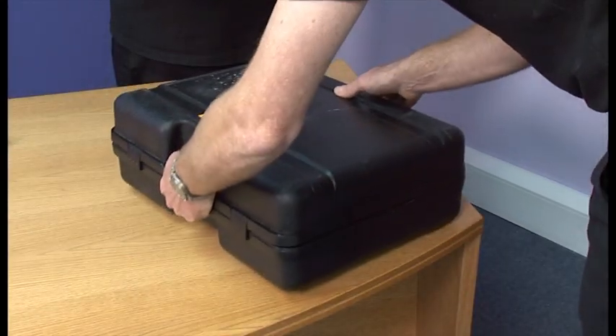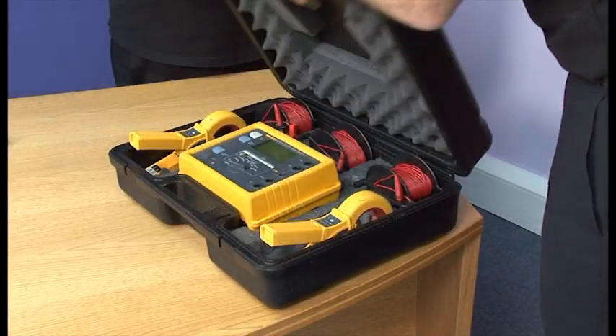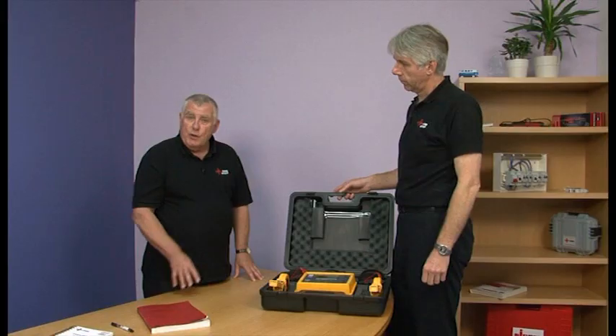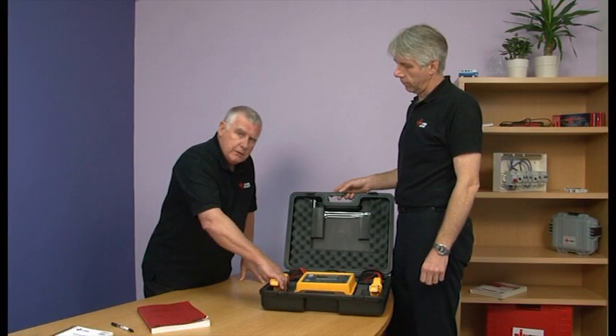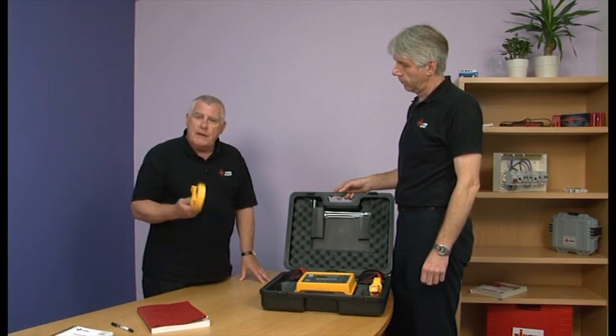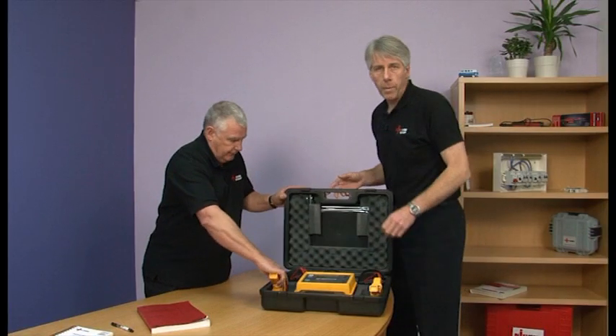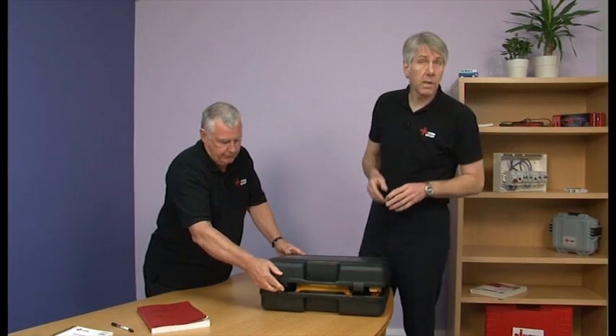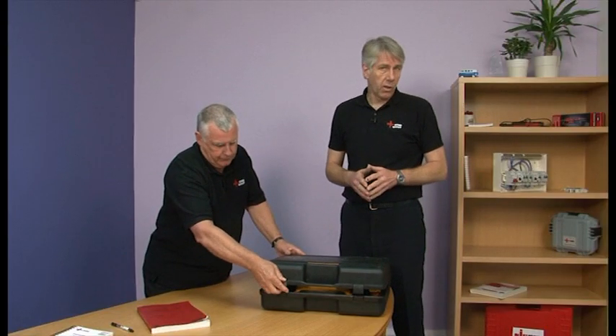However, recent developments in test equipment have also introduced a new non-invasive test where there is no need to disconnect the earthing conductor or connect to live terminals. You can instead use clamps. So an overall safer approach to obtaining the earth electrode resistance. Remember that the resistance value you get should be as low as practicable, and that values above 200 ohms may become unstable, particularly in dry or frozen conditions.